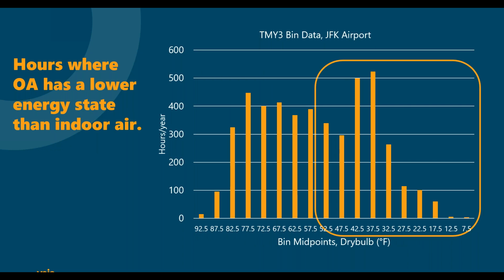And so similarly, in these zones where you have heating and cooling, there's over about 2,200 hours per year when that outdoor air has a lower energy state. So now you're illustrating why that ventilation load has a significant component on thermal energy use. And this really is a way to bring some visibility into that ventilation energy that a customer could be using.